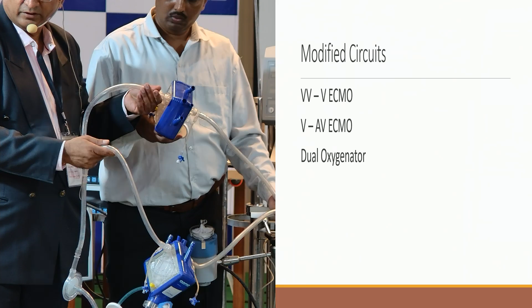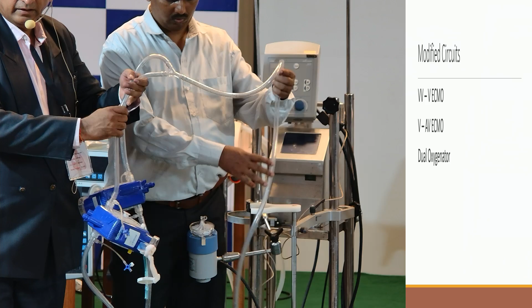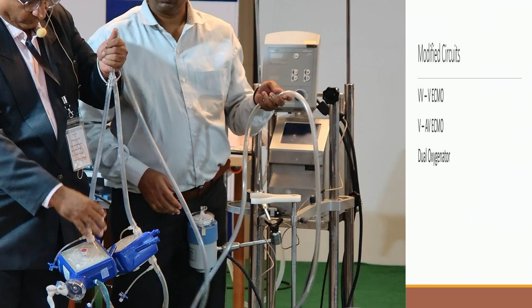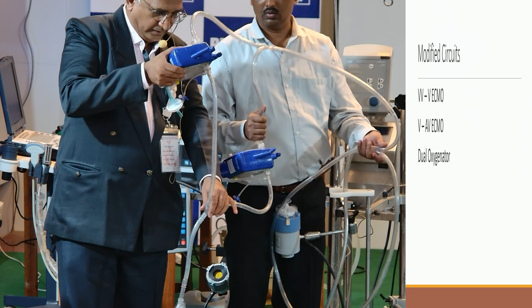Post pump, it is connected to the oxygenator. So this is connected to oxygenator in, or the blood in. It gets connected from the pump to the oxygenator. This side is negative pressure. Remember, before the pump everything is negative pressure. So if you open up any of these lines, it is going to suck air because it is like a vacuum. So this is a negative pressure line, and if by chance, by mistake, this three-way opens, it will suck a lot of air.